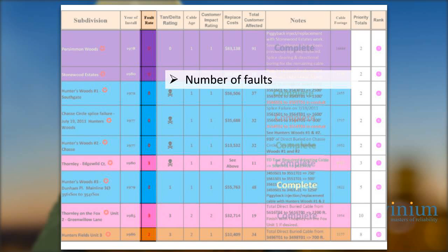The next thing, which I think is very special with what Steve has embraced, is determining the insulation quality of these old cables using VLF tan delta. For those unfamiliar, VLF is very low frequency, 0.1 hertz testing, and tan delta is essentially a power factor test for the cable insulation value. There are IEEE standards for new cables that we reference when testing before and after.